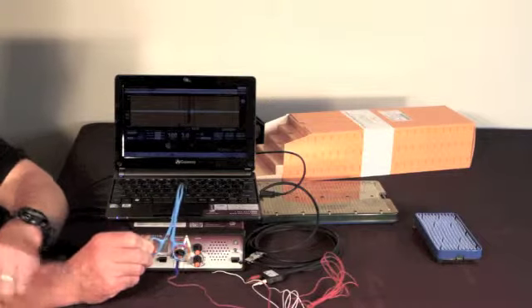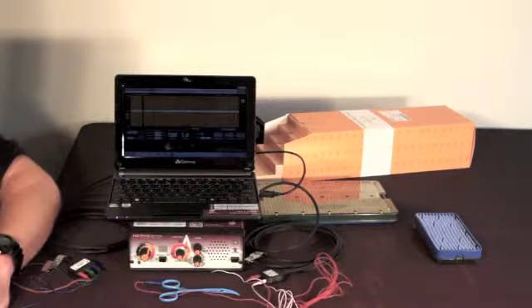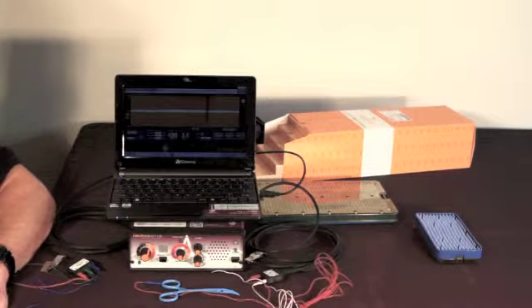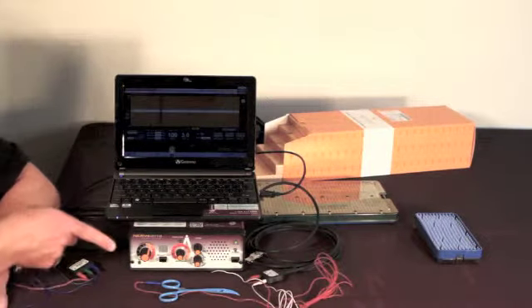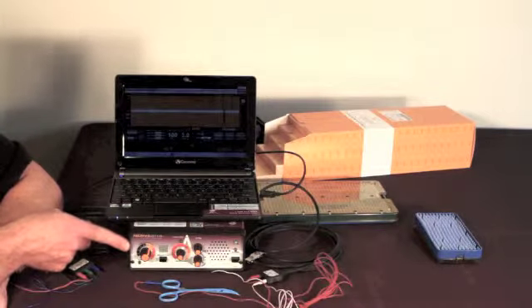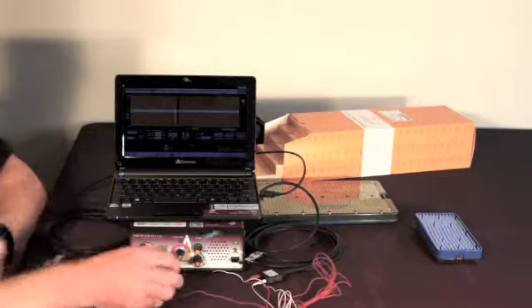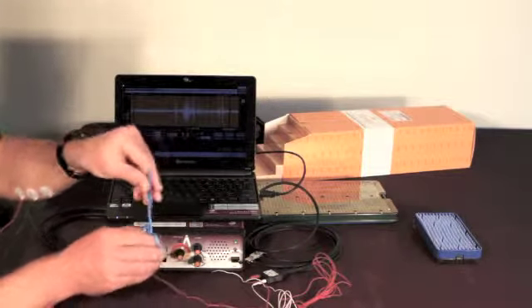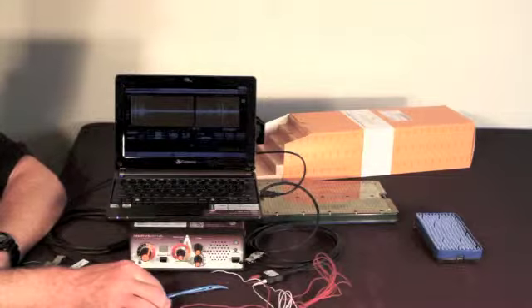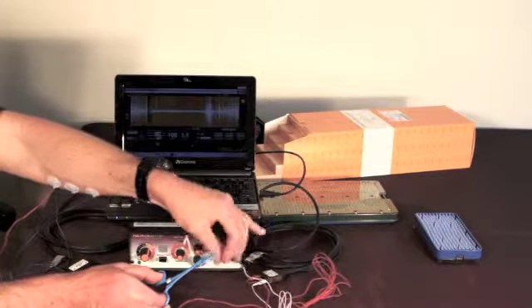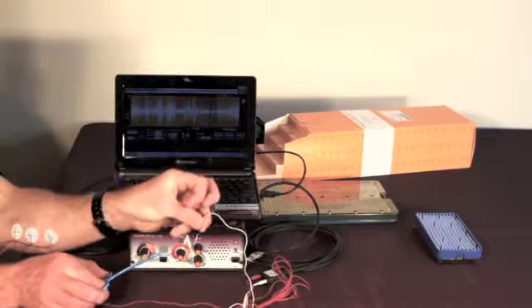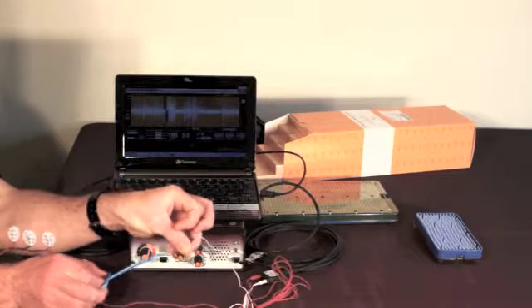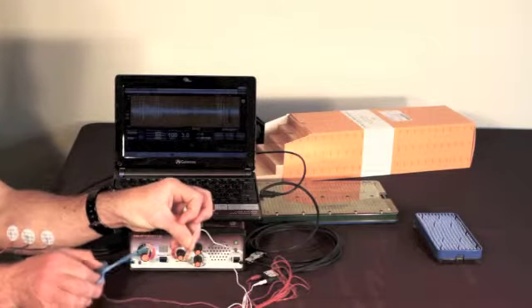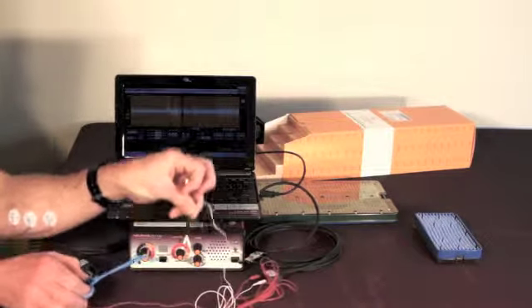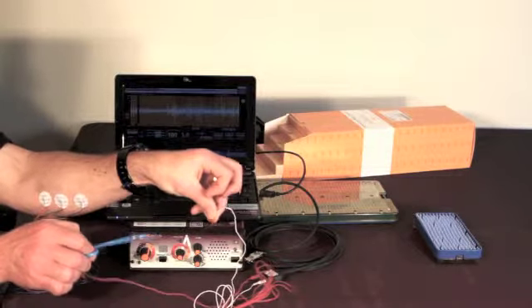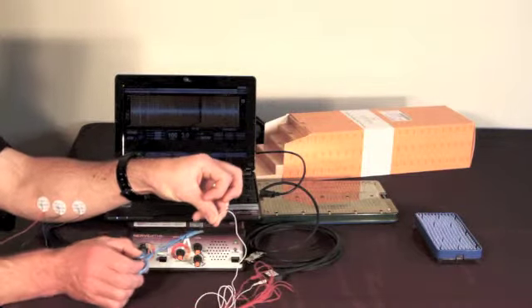When the surgeon stimulates with this probe to elicit an evoked response, what the Nerveana is doing is delivering to the patient the rated amount of electrical signal in milliamps. It's being delivered through the tips of this instrument, and it's being delivered at a rate of 4 times per second. The electrical currents are being delivered and measured in return to the machine for that measurement through this needle that's in the shoulder. So I'm going to bypass the patient, so to speak, which would normally be in between the needle and the probe.